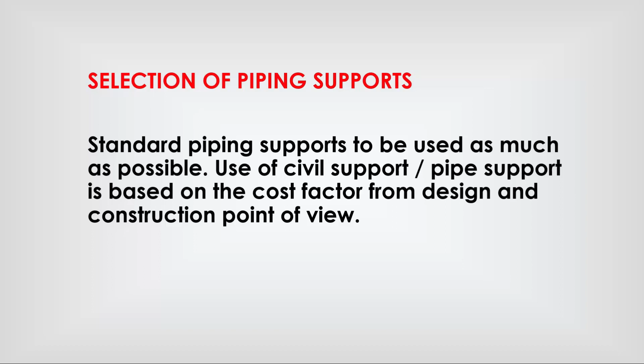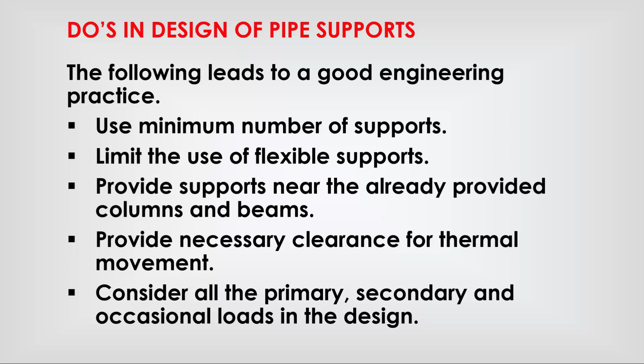Do's in designing pipe supports. The following leads to good engineering practice. Use minimum number of supports. Limit the use of flexible support. Provide supports near the already provided columns and beams. Provide necessary clearance for thermal movement. Consider all the primary, secondary and occasional loads in the design.